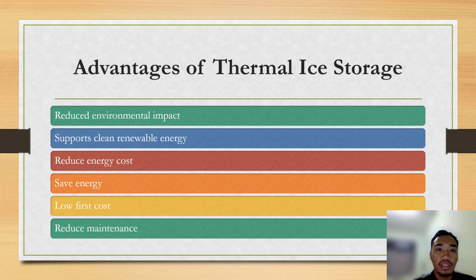The next advantage is it is low first cost because thermal ice storage can use smaller chiller and heat rejection equipment. It also has reduced piping and pump size. The ducting and fan size is also reduced, and generator size is also reduced. So it can contribute to a lower first cost.